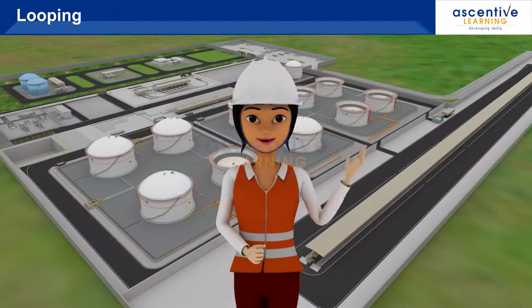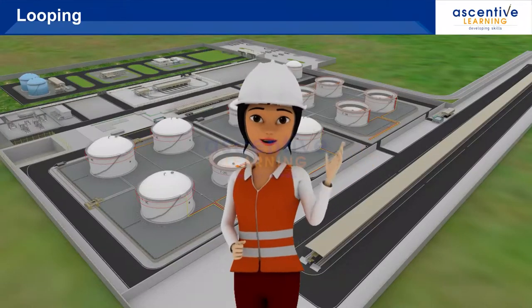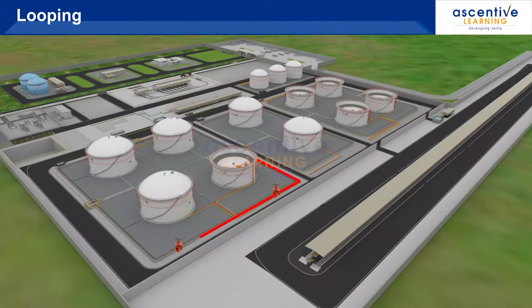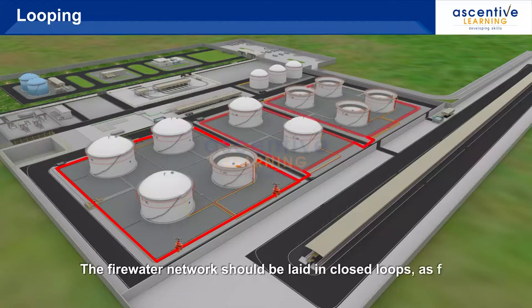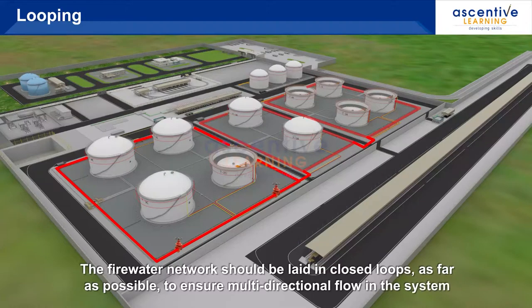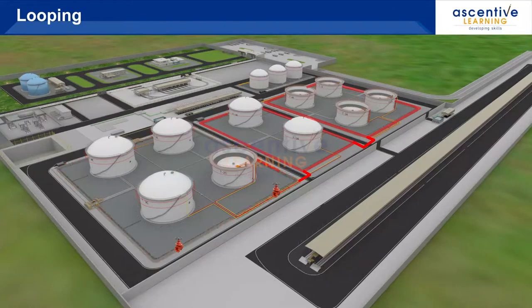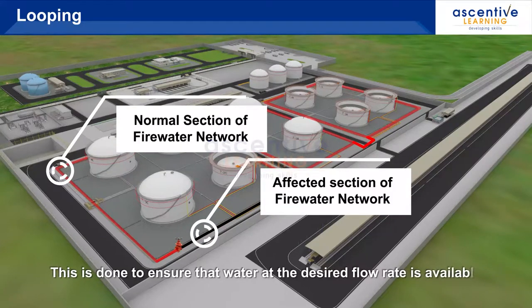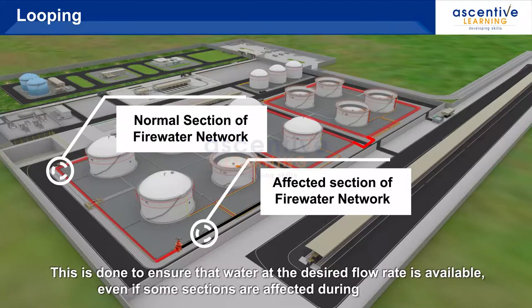Let us learn about the important points while designing a fire hydrant network. The fire water network should be laid in closed loops as far as possible to ensure multi-directional flow in the system. This is done to ensure that water at the desired flow rate is available even if some sections are affected during the incident.